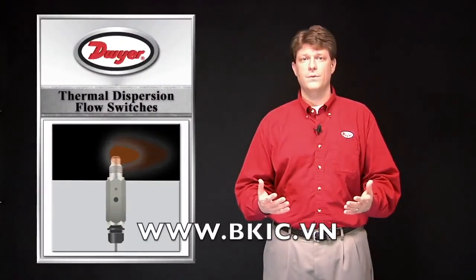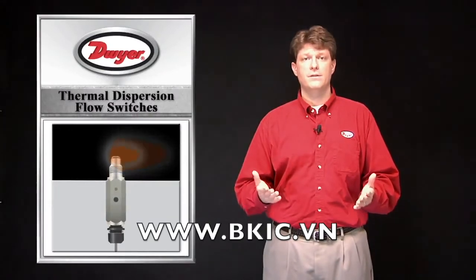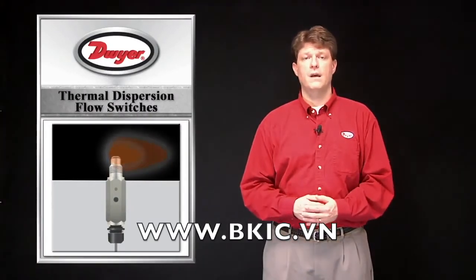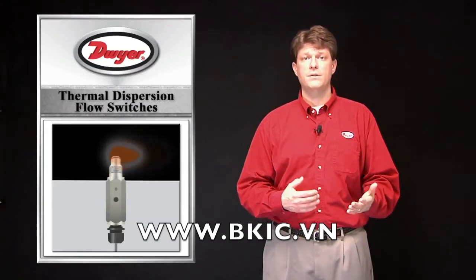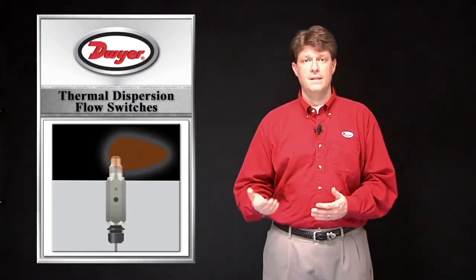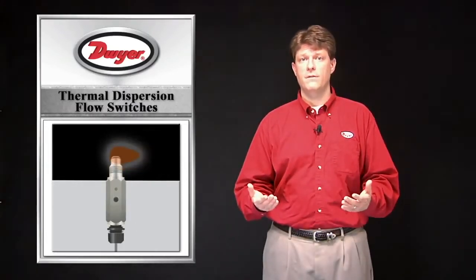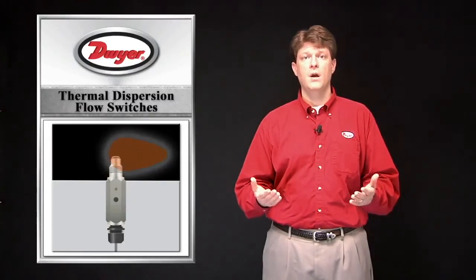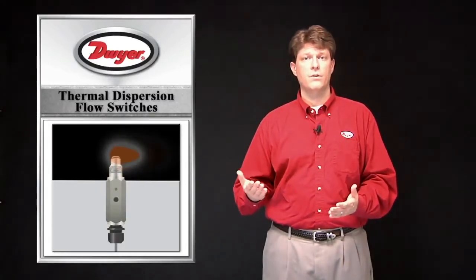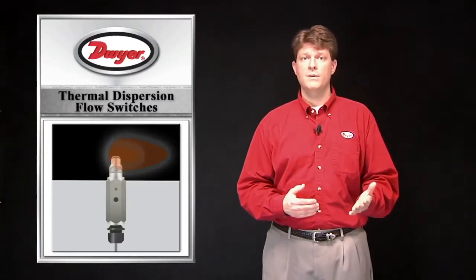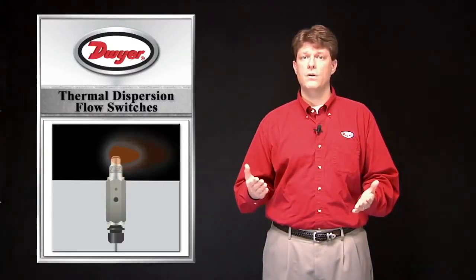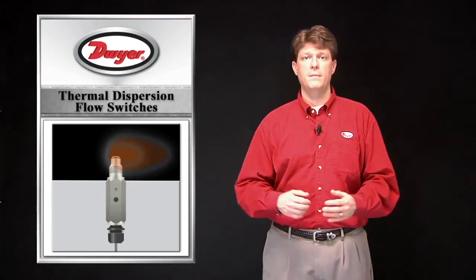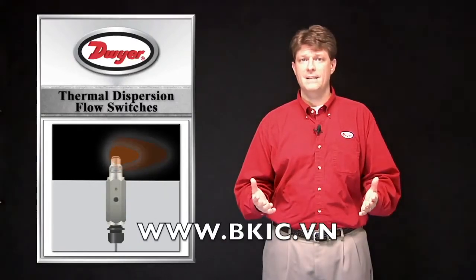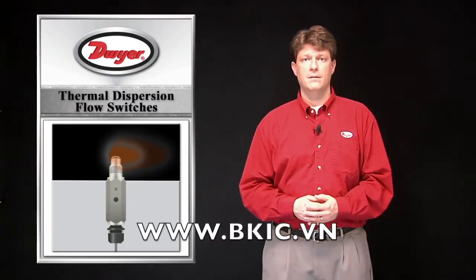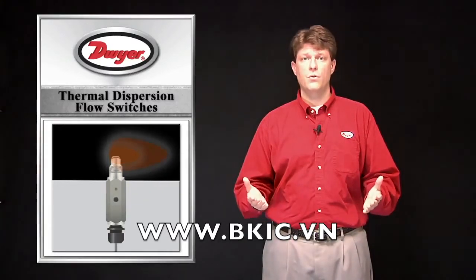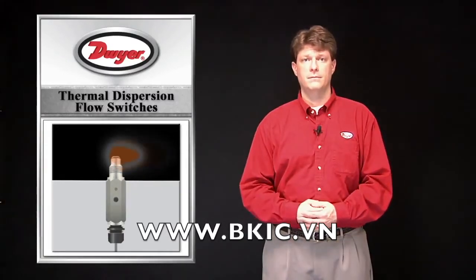The TDFS flow switch uses a single platinum RTD sensor that is heated and cooled over several steps. First, the RTD measures the temperature as a reference. Second, the RTD is heated to a fixed differential temperature above the media temperature, creating a temperature gradient and storing thermal energy. Third, the probe is allowed to cool down from the flow to another fixed differential temperature above the media temperature. A thermal decay time constant is then calculated. Last, the probe is allowed to cool before the next cycle of measurements.